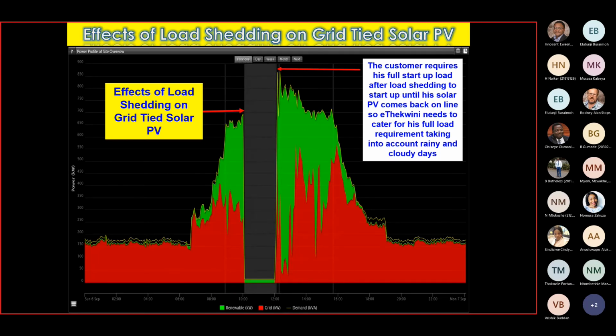That's a critical thing that needs to be taken into account, especially with larger PV systems coming into the network. So in terms of planning, you still have to plan for the customer's full load irrespective of the PV system they have, because when you switch back on after load shedding or an outage, you still need to feed the customer's full in-rush current and full startup load until the PV system can come back online.